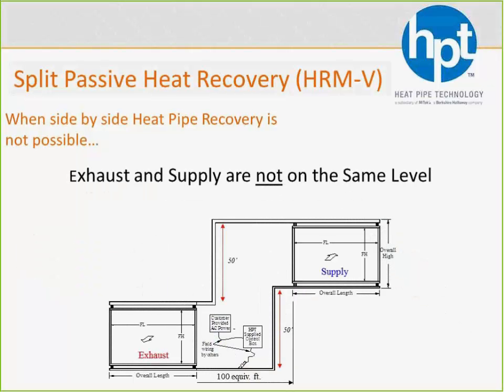We can also work with an elevation change. We can actually get up to about 50 feet in elevation. And when we have elevation, that means we've got some gravity helping keep the refrigerant moving. So we can actually run a little bit further. So if we get up to 50 feet of elevation, that means we can get about 100 feet of an equivalent run in, which is nice.